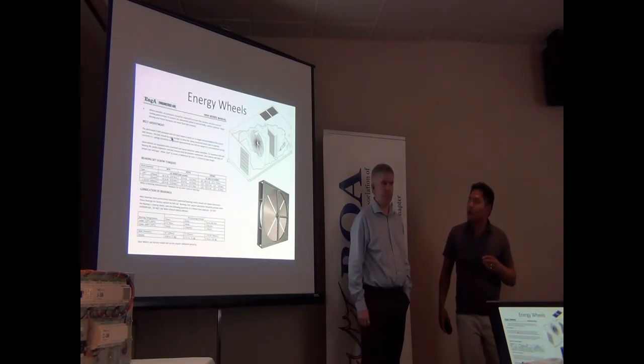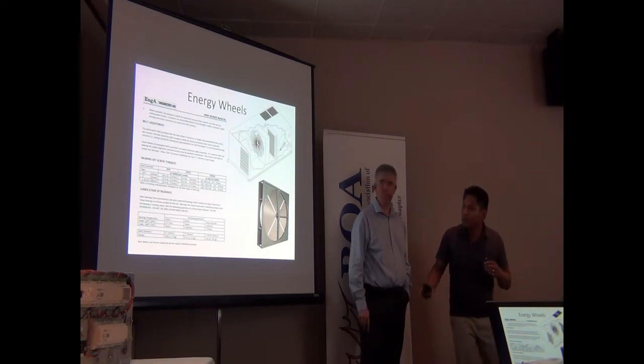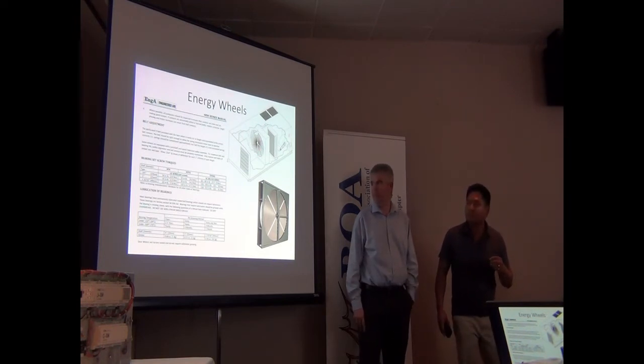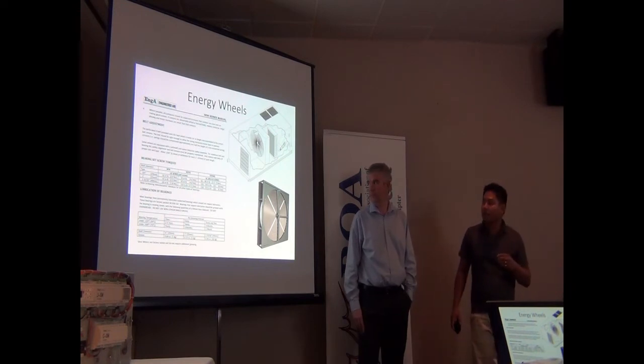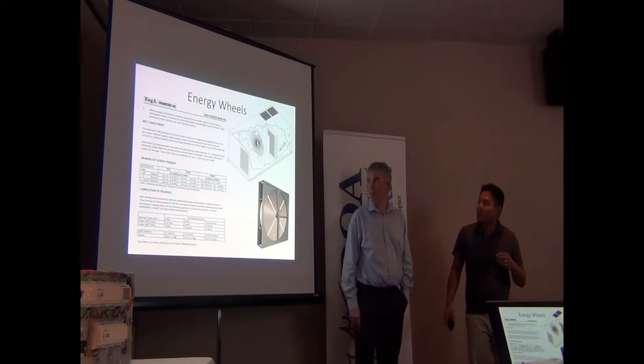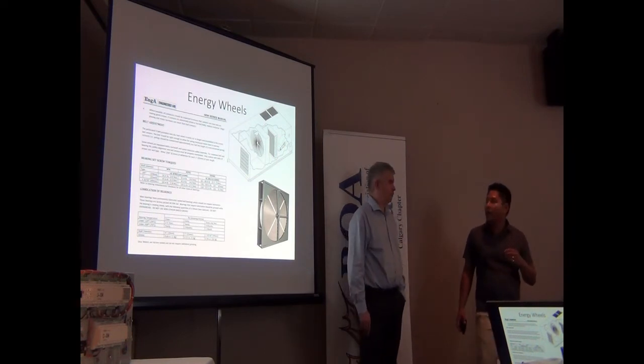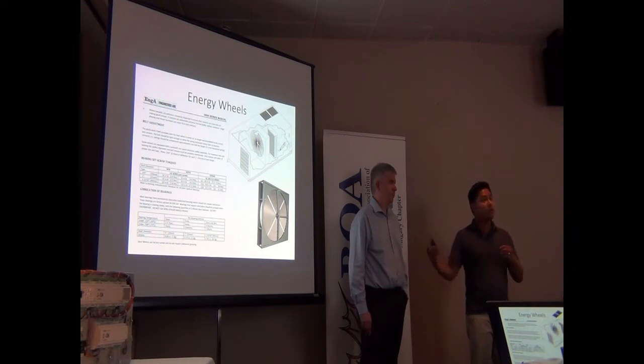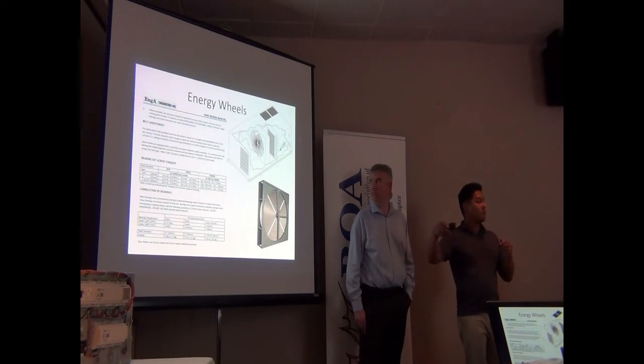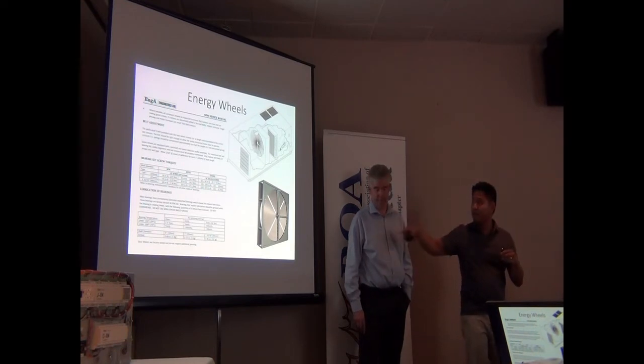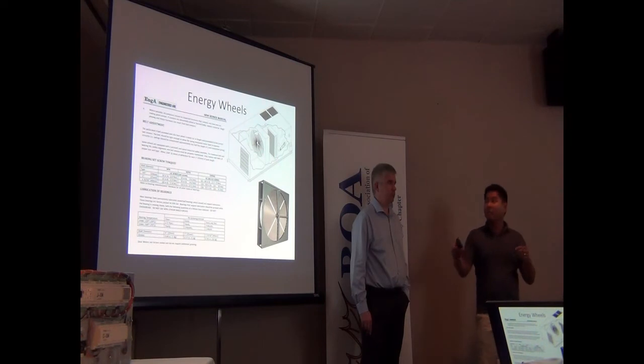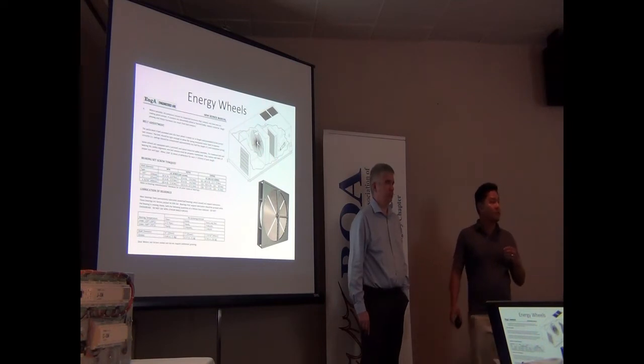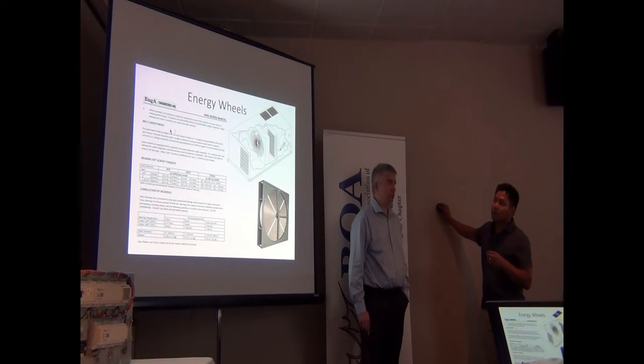Same goes for energy wheels. Our manual tells you the lubrication intervals, set screw torques, and all that stuff. They're not too bad, but they are heavy. They can pull out from the side, you can remove the panels off the casing. I believe the way we drop them in is from lifting lugs above the heat wheel itself, so if you have to crane it, there are lifting lugs already connected to the heat wheel.